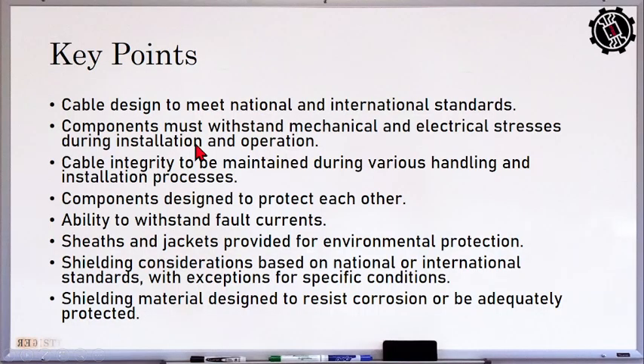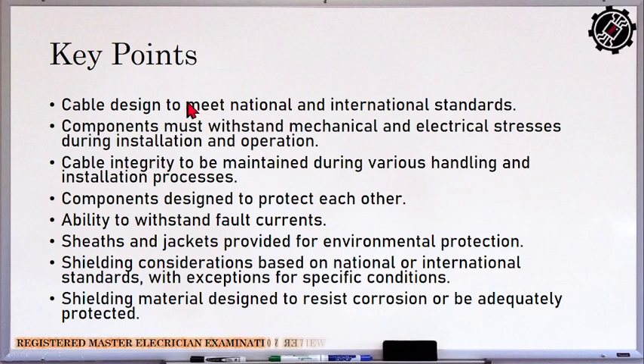Okay, so this is the summary ng mga provisions kanina. Cable is designed to meet the national and international standards. The components must be able to withstand mechanical and electrical stresses. Then the cable integrity is to be maintained during the handling and the installation process. Then the component design of our cable system must be able to protect each other from damage and must have the ability to withstand fault currents. Sheaths and jackets should be provided for environmental protection. Tapos, shielding considerations.